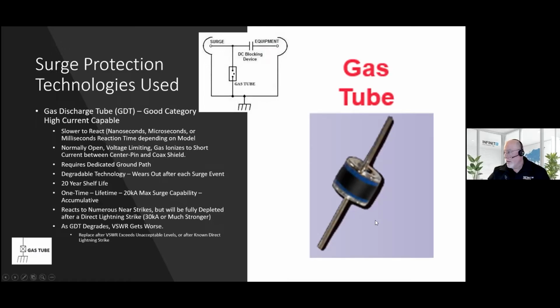Well, the one thing about gas tubes is they're degradable. So they wear out a little bit after each surge event, and there's usually no indicators to tell you when. So how do you test for that? With VSWR testing is how you do that. So as this degrades, the VSWR gets worse, and at some point you make a subjective decision on when to replace it, and you do.